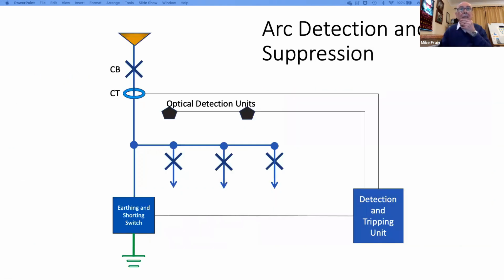I'll just talk for a few minutes about this one. This is arc detection and arc suppression. Sometimes arc detection is used on its own without the suppression to trip upstream devices. I've come across that several times. But several manufacturers now have produced innovative ways of reacting to an arcing fault by effectively creating a zero impedance short circuit across the bus bars of equipment. Yes, you heard me right first time. They're going to make a short circuit across all three phases and sometimes to earth as well. So dependent upon the method used for sensing the development of an arc, they can be incredibly fast, and manufacturers claim disconnection times as low as 4 milliseconds.